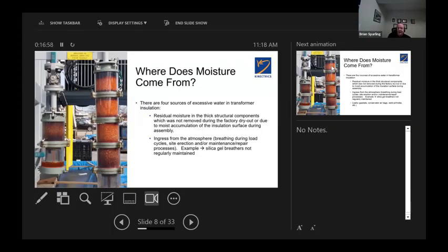And my favorite are leaks, through gaskets, through conservator airbags that have lost it, from weld pinholes. Understand what a leak is. When I look at transformers, when I walk in a substation, I look for leaks. And if I see leaks, I point it out, and I get told, well, yeah, that's just a little one. It's a seep, and it's not hurting the environment because we're out in the middle of nowhere. I said, wait a minute.